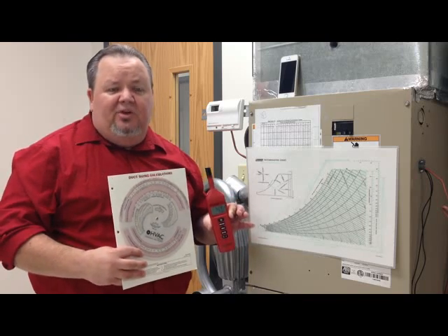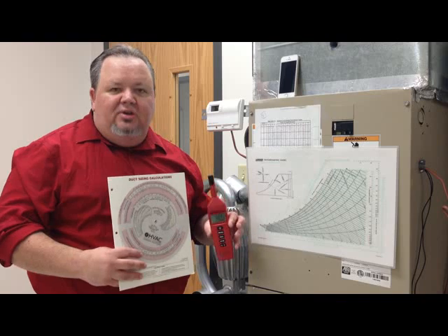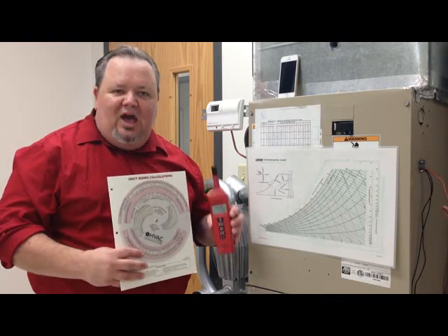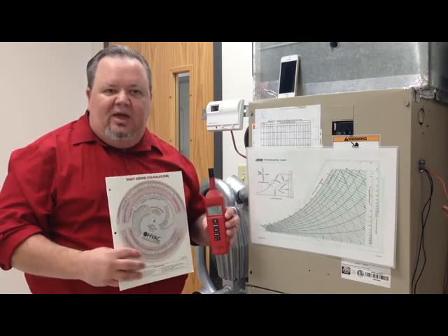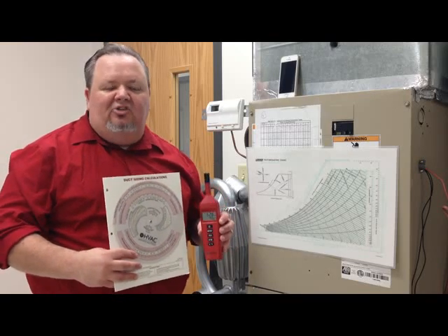For example, with some knowledge of psychrometrics, we can perform the total heat test. The total heat test allows us to know exactly how much heat an air conditioning system is absorbing from the house and then rejecting outside, or how well it's actually working.